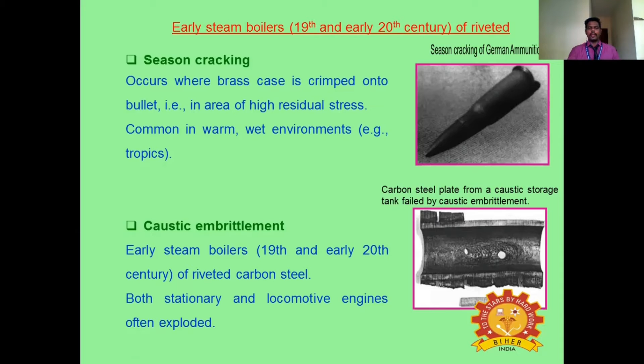And coming to caustic embrittlement. Caustic embrittlement corrosion is very important. If you use concentrated sodium hydroxide in hot water for a boiler, it will create minute hair-like cracks inside the boiler because of that high concentration of sodium hydroxide. Because of that, the tank fails and becomes brittle. So this type of corrosion comes under caustic embrittlement. You can see this is a carbon steel plate from a caustic storage tank that failed by caustic embrittlement. This is applicable to both stationary and locomotive engines, which often exploded because of that high concentration of sodium hydroxide.